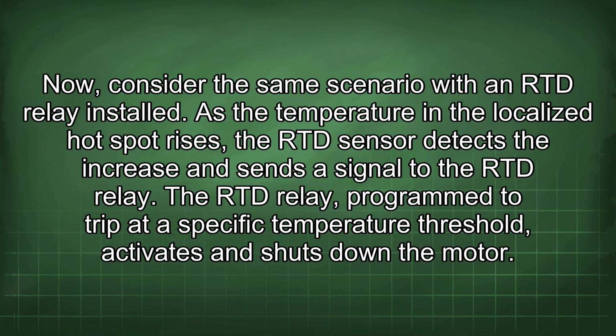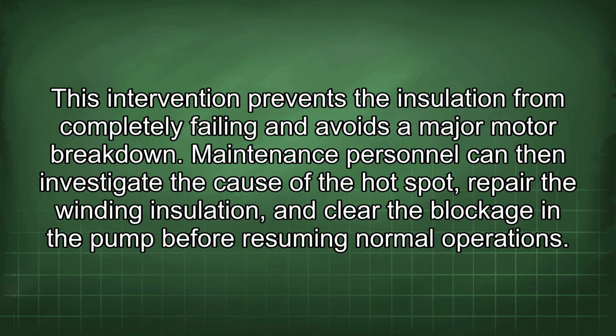As the temperature in the localized hotspot rises, the RTD sensor detects the increase and sends a signal to the RTD relay. The RTD relay, programmed to trip at a specific temperature threshold, activates and shuts down the motor. This intervention prevents the insulation from completely failing and avoids a major motor breakdown. Maintenance personnel can then investigate the cause of the hotspot, repair the winding insulation, and clear the blockage in the pump before resuming normal operations.